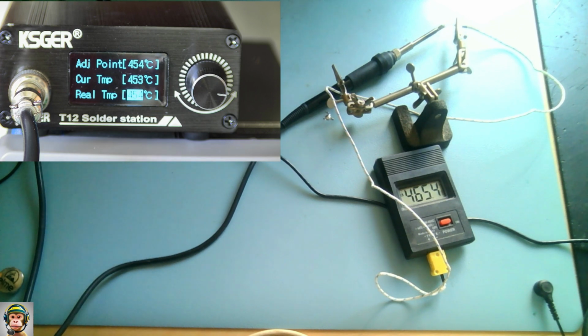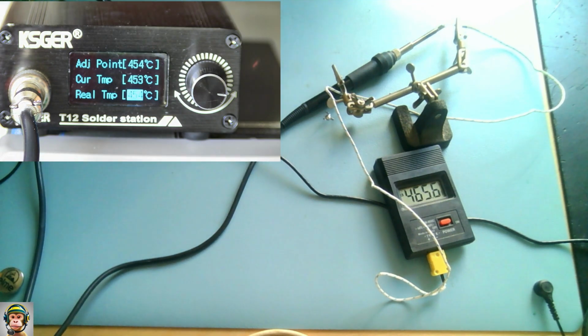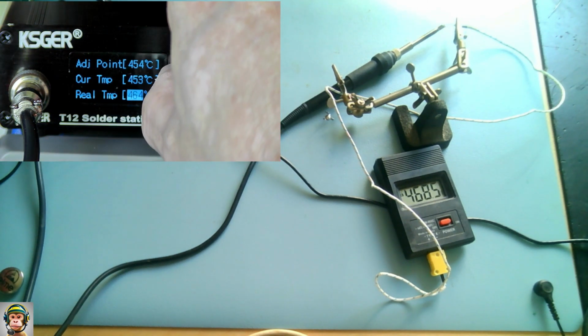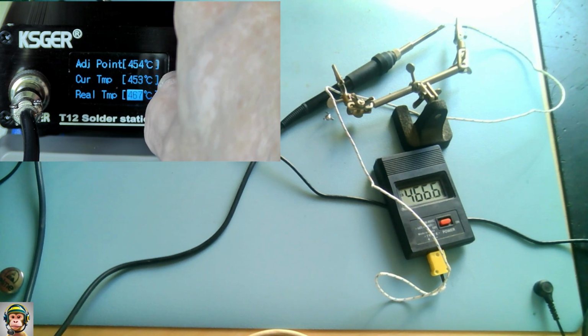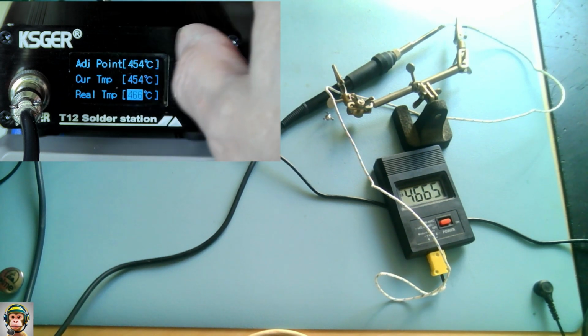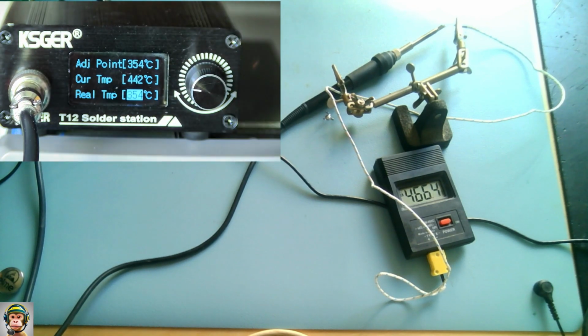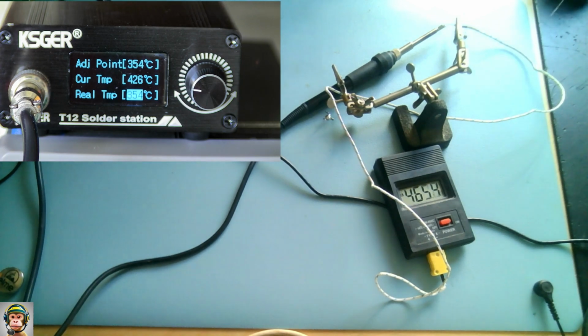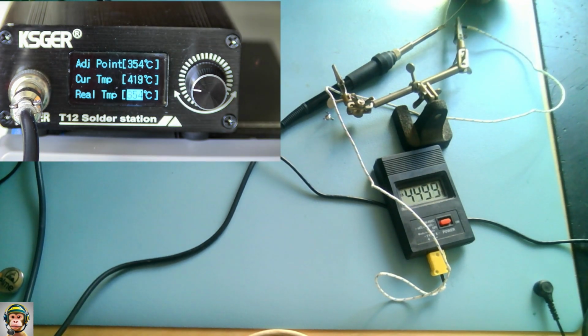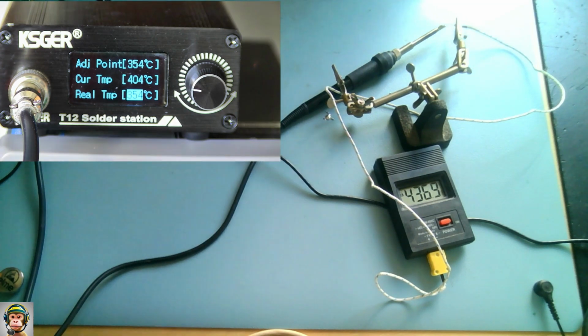You'll see that the temperature stabilized on 465 degrees Celsius. Enter this in the real temp field by turning the knob in the right direction. Press the knob to go to the next set point. We repeat the previous step for 354 degrees Celsius.